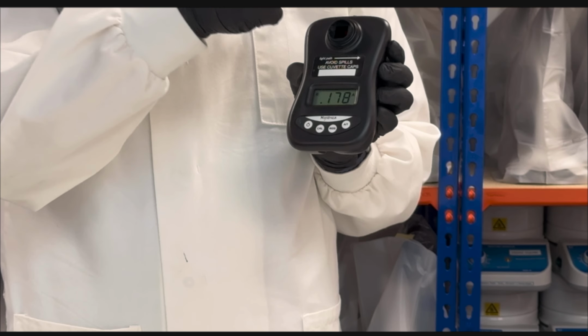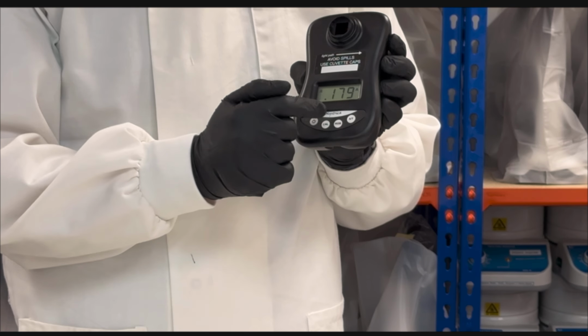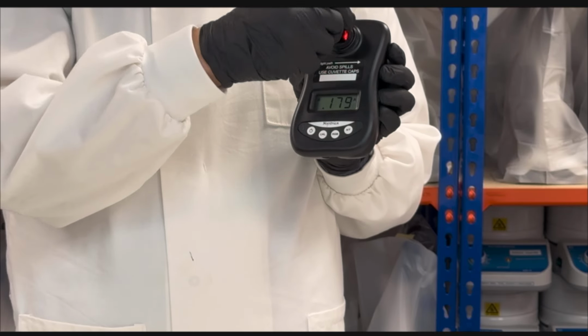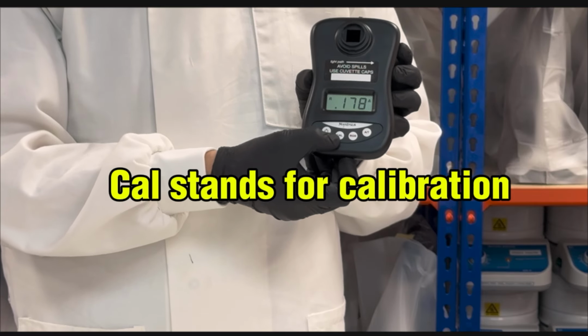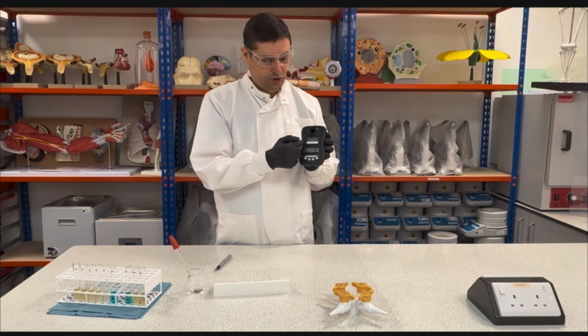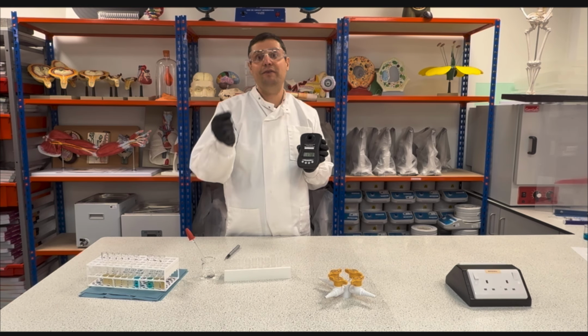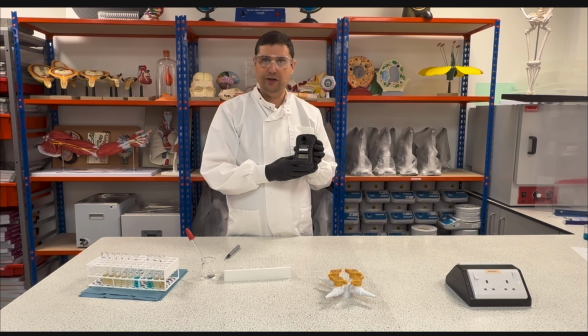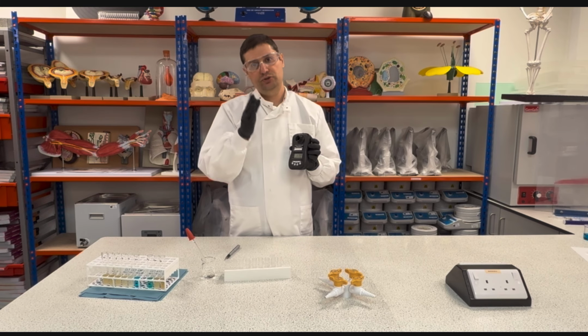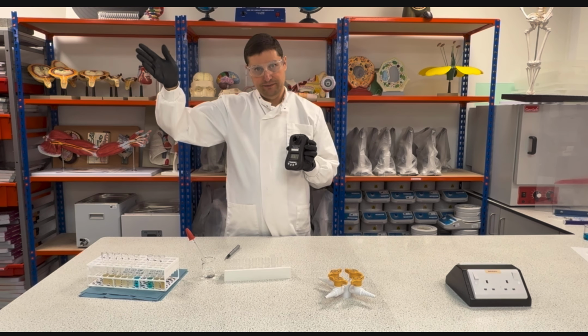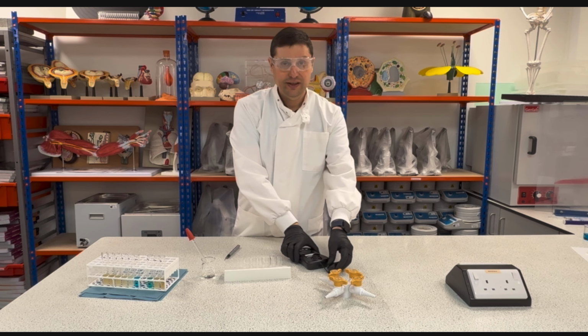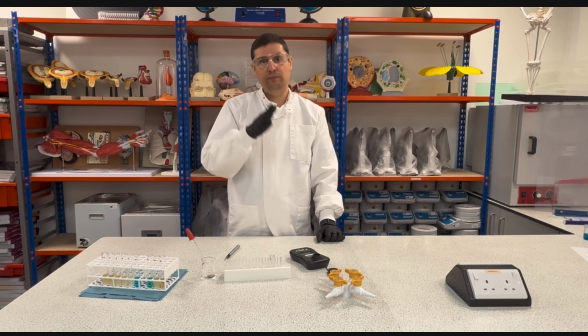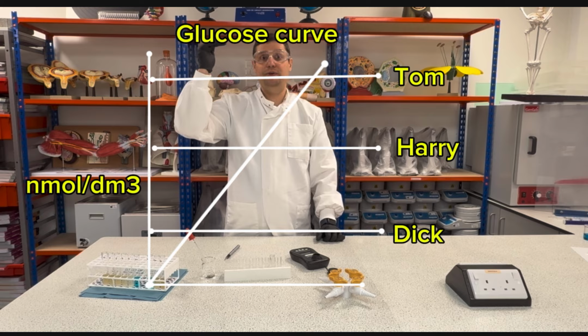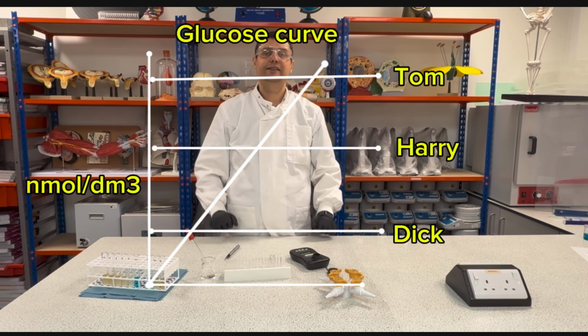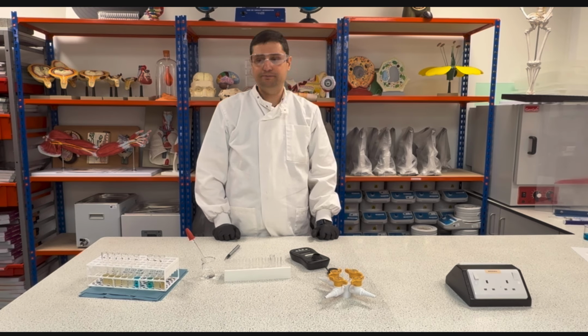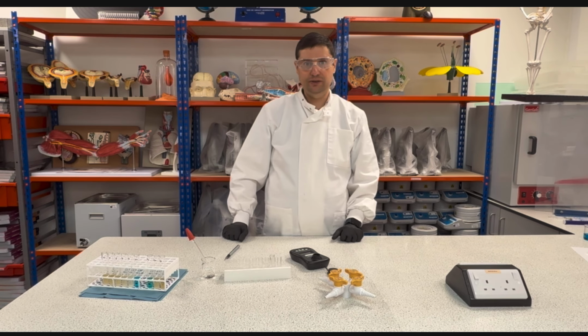So now I will put back here in the table. I will place my cuvette with water inside, close it, and I will press Cal for calibration. Right after calibration, this is gonna zero everything, and then I will place my first sample, that's the 0 glucose, and then I will go for 0, 2, 4, 6, 8, 10. I will write my results, and after that I will do my Tom, Dick, and Harry, and I will compare the results between the three with the curve that I did, and then I will be able to find my unknown results for my urine sample.